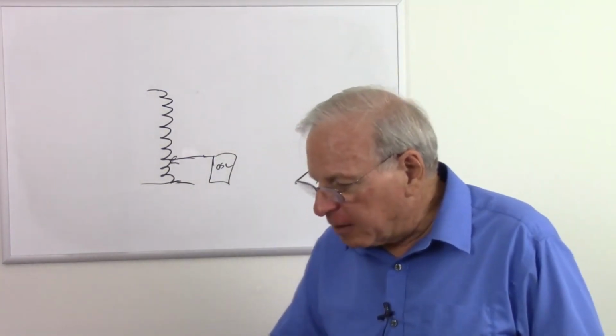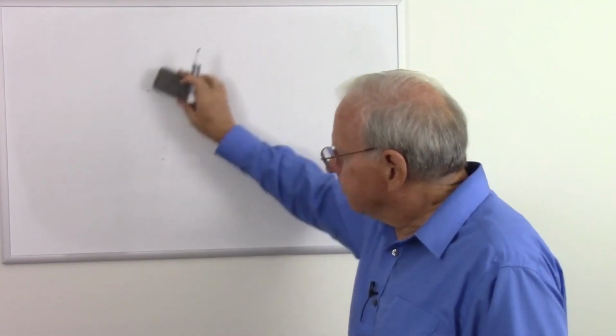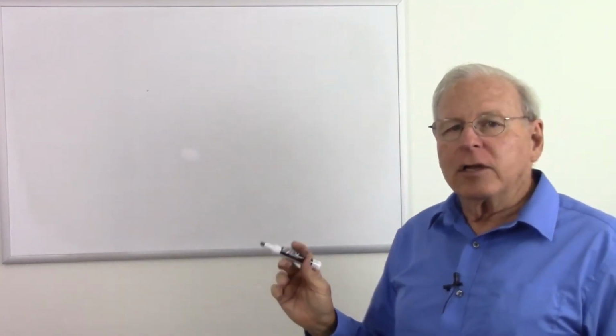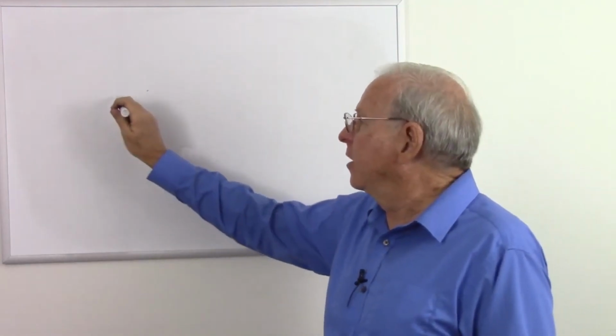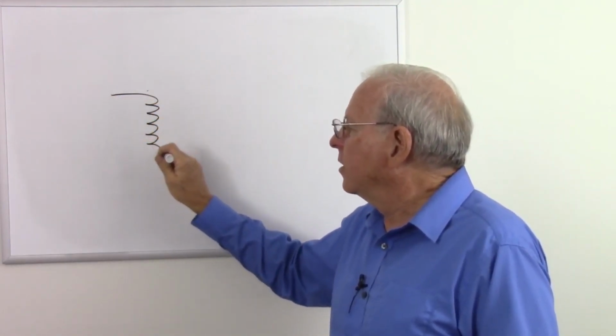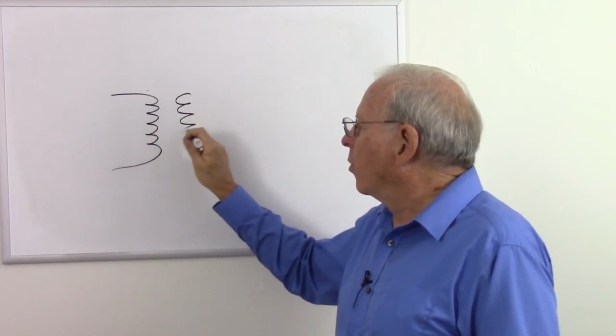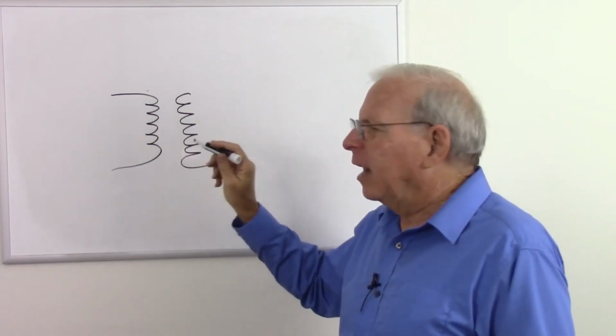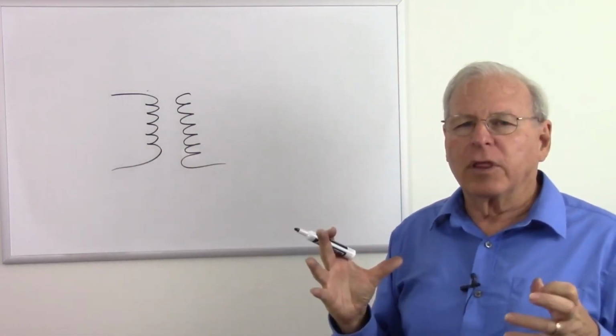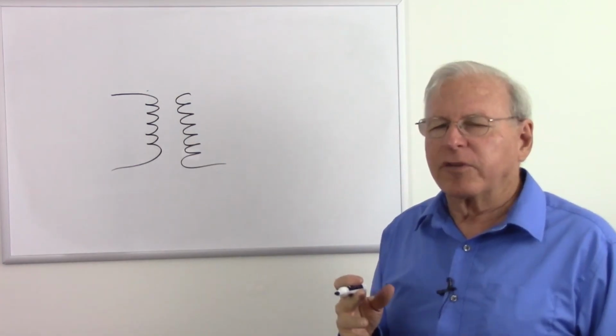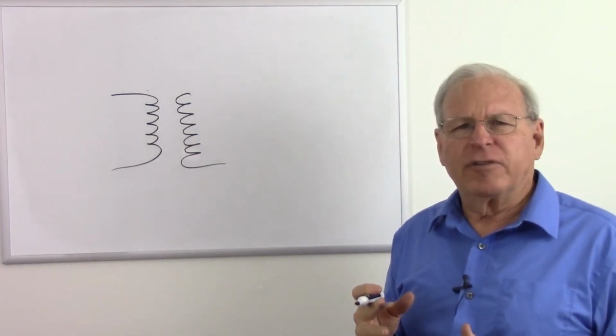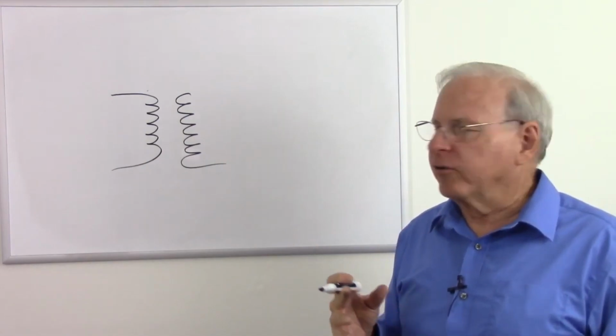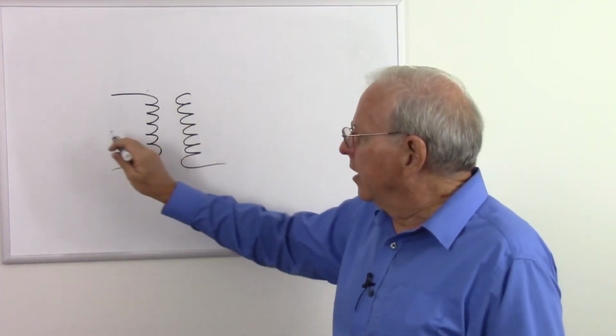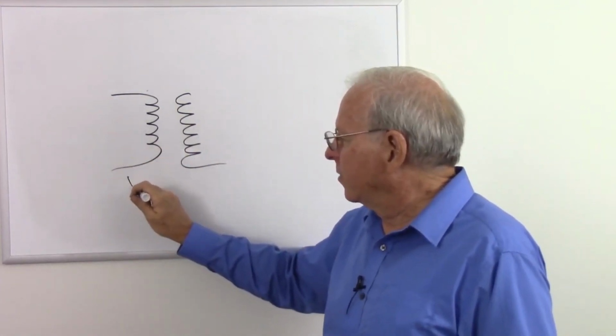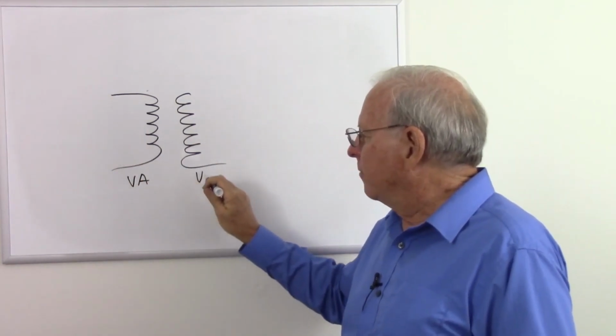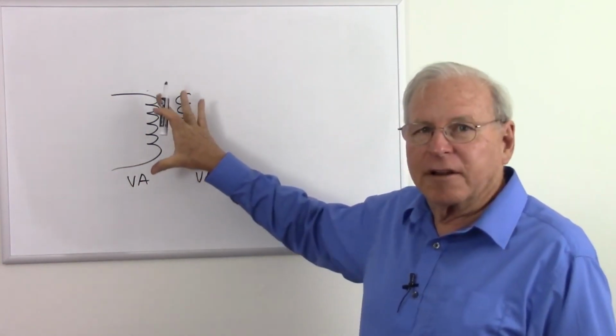So let's talk a little bit about efficiency before we move on. Transformers are very efficient in transferring energy without losing it in some form or another. Good high quality power distribution transformers have an efficiency of something like 99.7%. What that means is volt amps go in, and volt amps come out, without a lot of heat coming out.